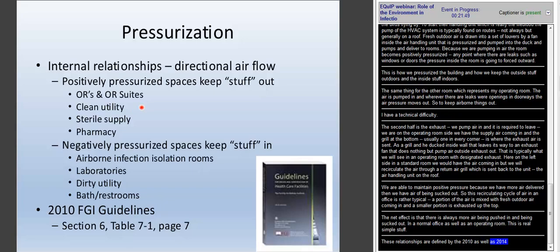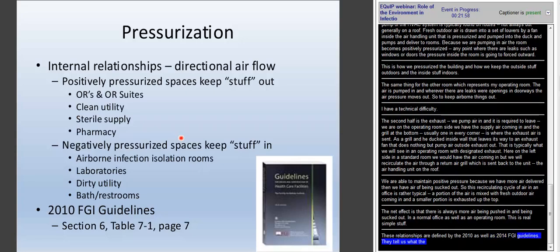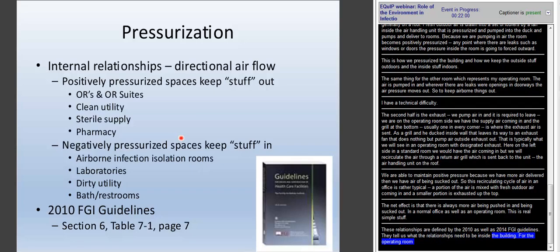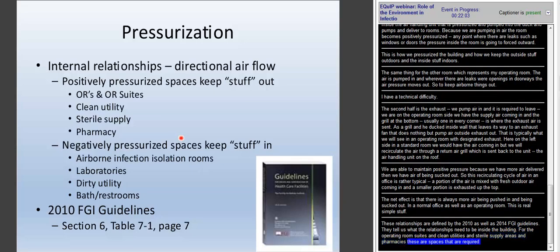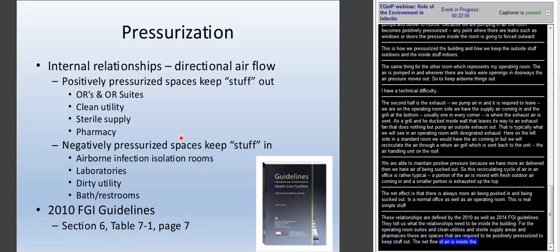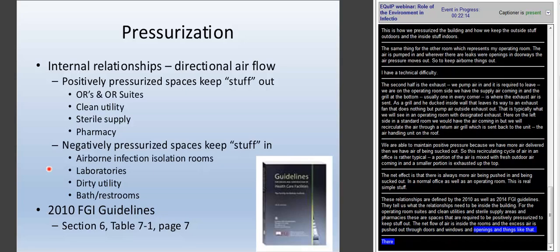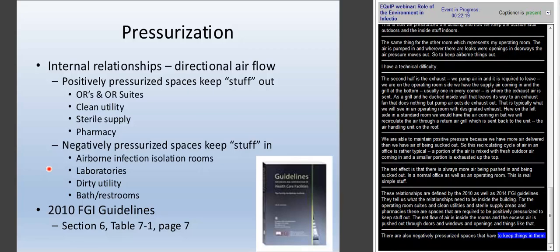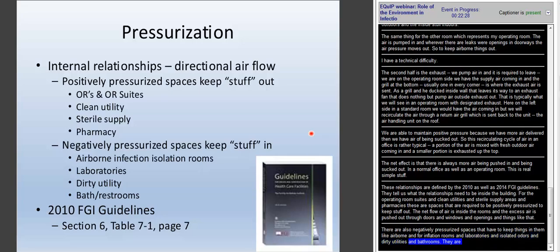For our operating room suites, our clean utilities, our sterile supply areas, and our pharmacies, these are spaces that are required to be positively pressurized to keep stuff out of them. So the net flow of air is into those rooms, and the excess air in them is pushed out through doors and windows and openings and things like that. There are also negatively pressurized spaces that have to keep stuff in them, like airborne infection isolation rooms to isolate the patients, laboratories to isolate odors, dirty utility, bathrooms. They're all required to be kept negatively pressurized, and that's all found in the FGI guidelines.